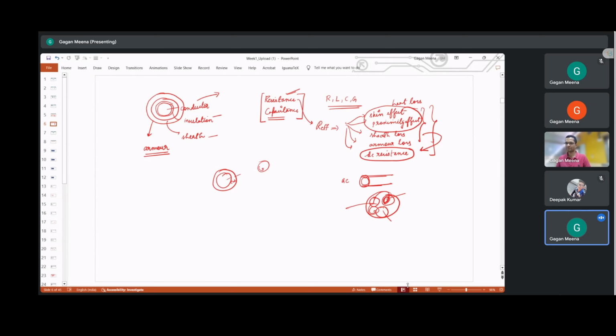Yes sir. Similar to transmission lines, in cables also we do transposition to reduce this effect. Eddy current and hysteresis losses depend upon the path length, so if we reduce the path length, we reduce the losses. So at certain intervals we try to do this transposition of the sheath, which is also called cross bonding in case of cables. So, this is done.